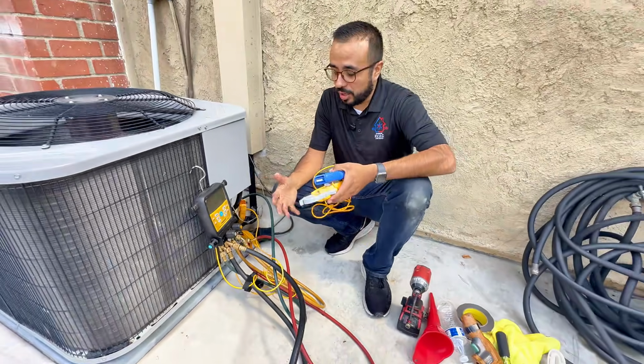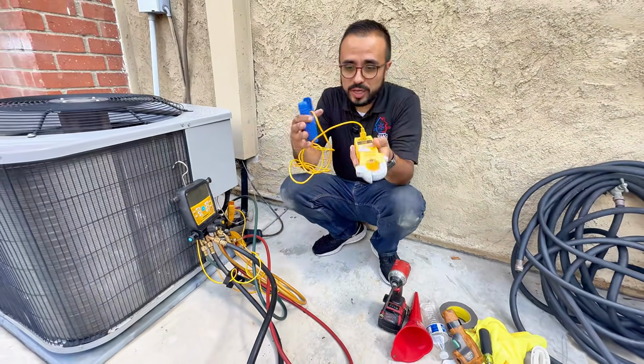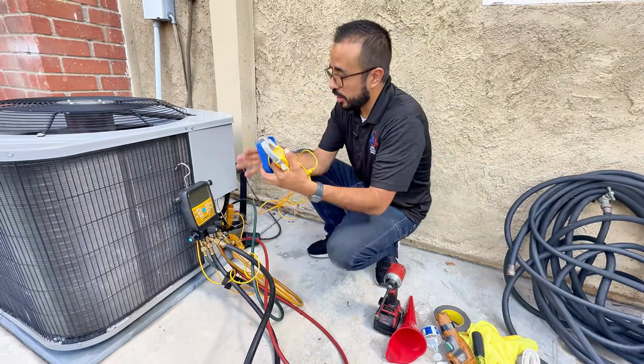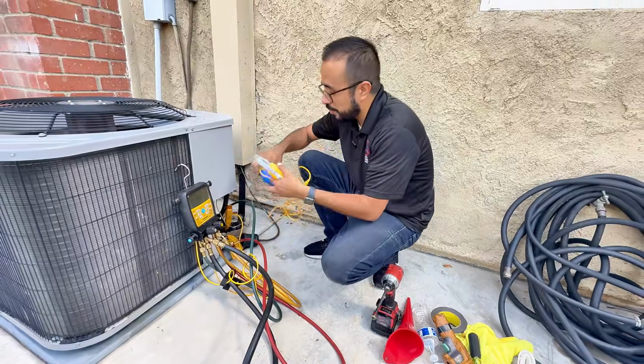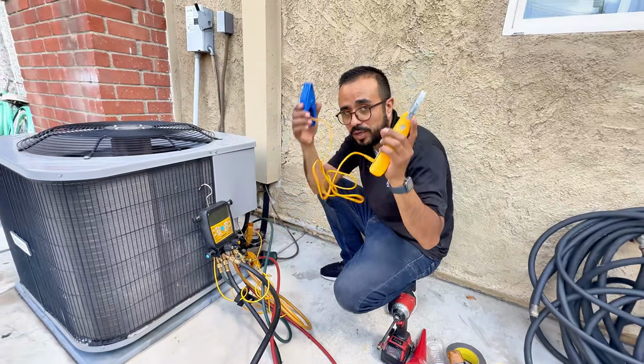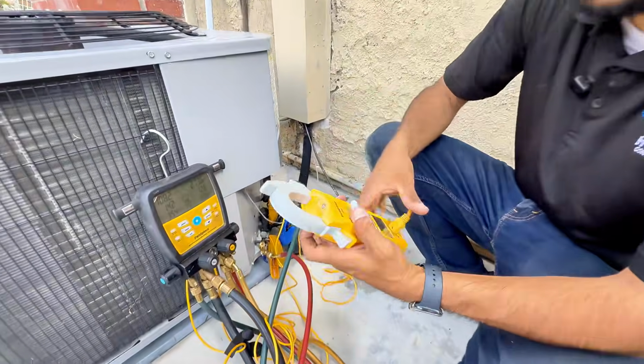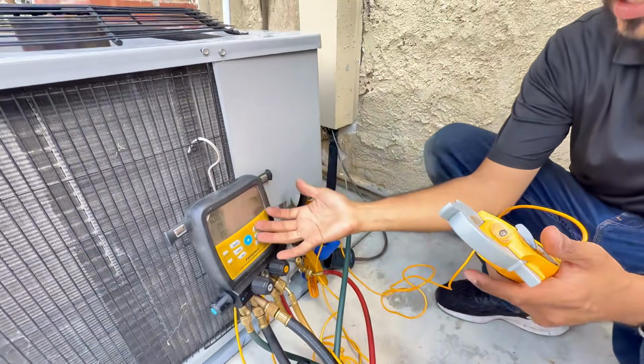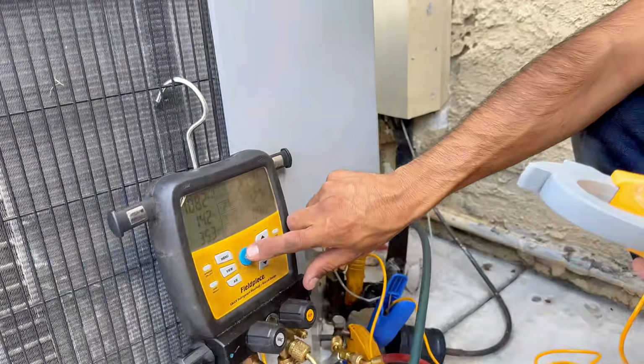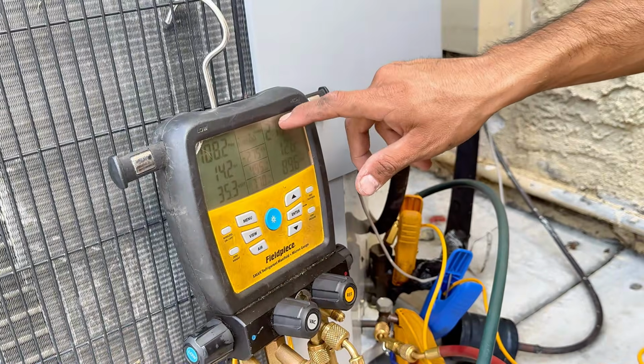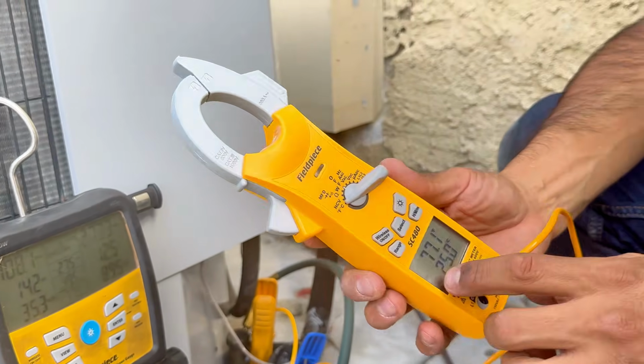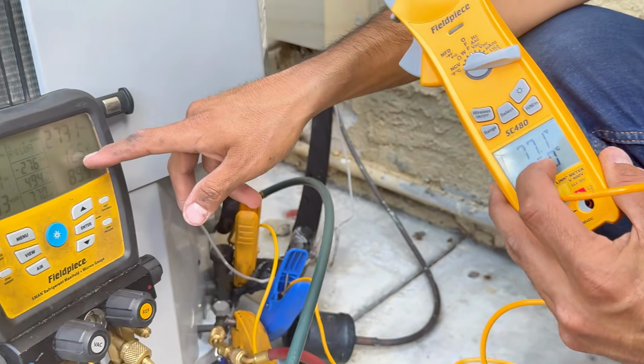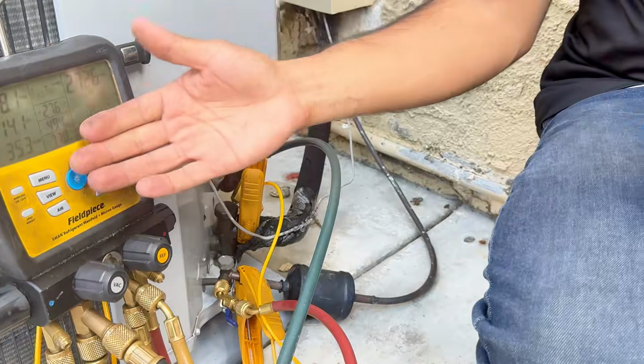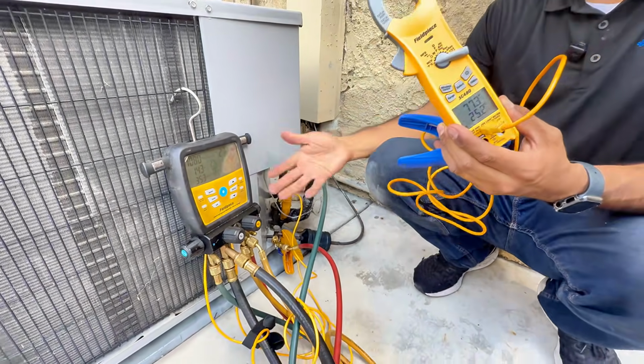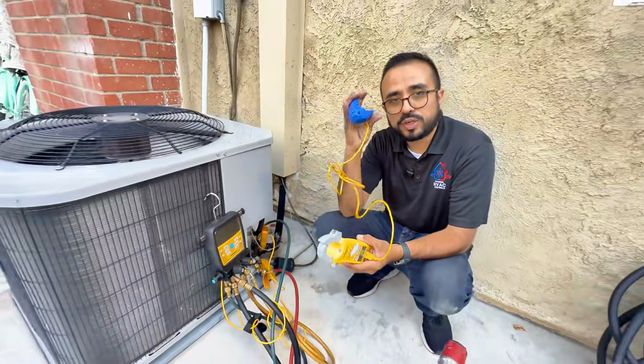There's different ones. But let's say you don't have digital gauges, and you only have analog. Well, with your meter, you can just buy this temperature clamp separately. So you get your analog gauges, you connect it to the system, and you can still get subcool and superheat, right? My meter, temperature clamp, connected right there. And let's say, hypothetically speaking, this is analog gauges. You convert your high side pressure into a temperature, 90 degrees, minus your liquid line temperature, 77, about a 12, 13 degree subcool. So you see, I'm able to do that. I don't need to get these to be able to check superheat and subcool. I can do it with a meter and the temperature clamp, right?